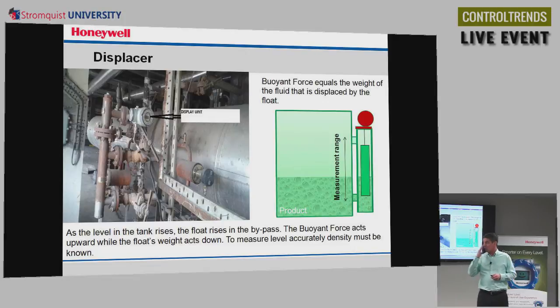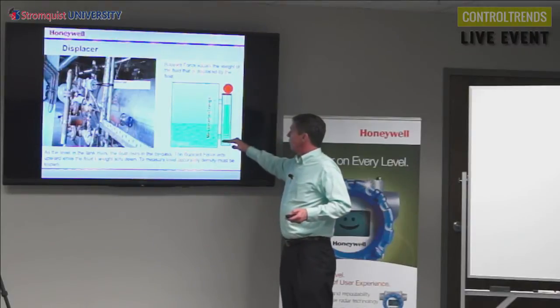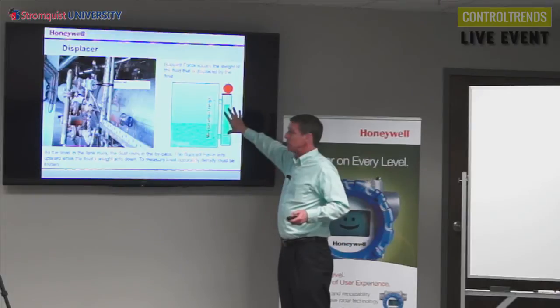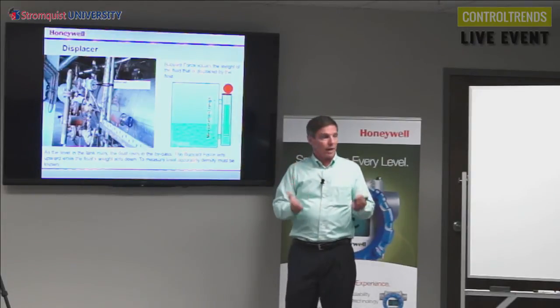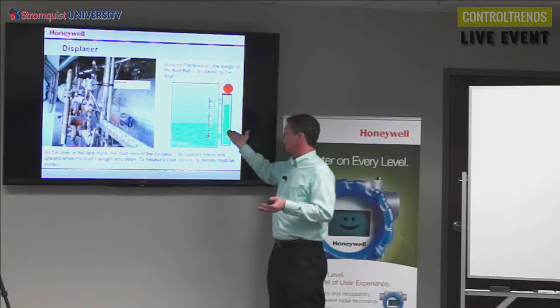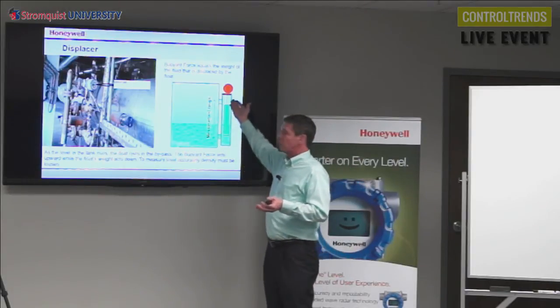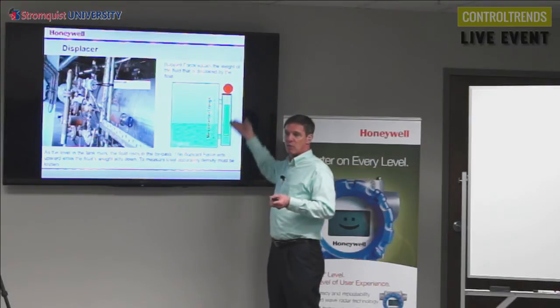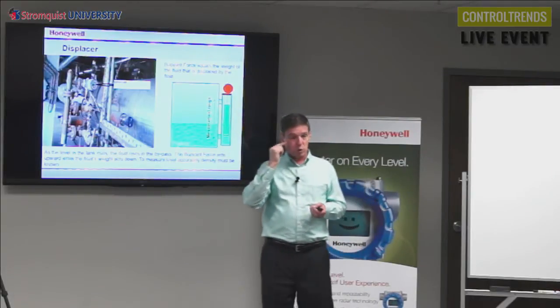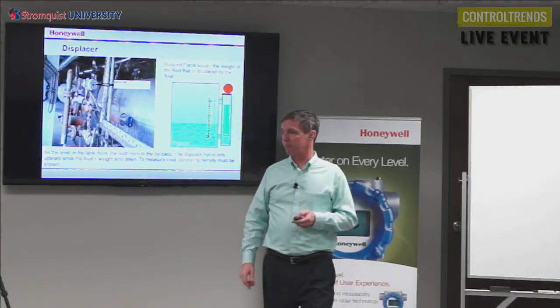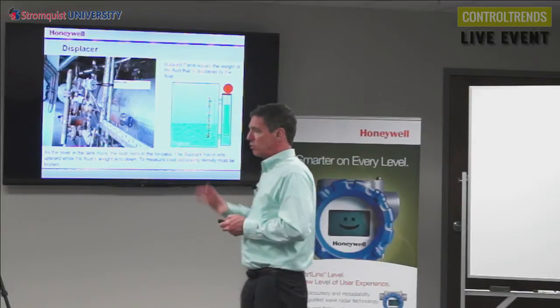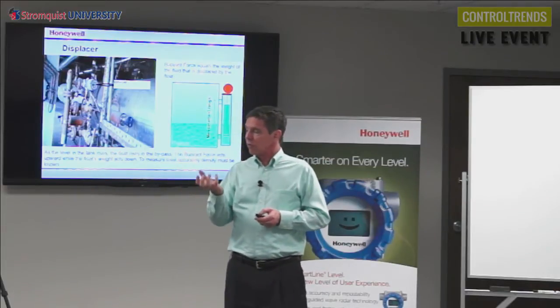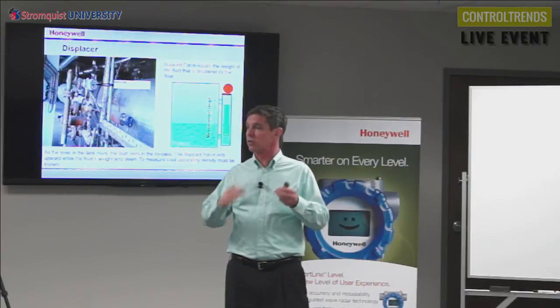But the way this works is off a buoyant force. So we're kind of measuring the weight of that float that's in there. That's a float that's right in the middle. It's on the end of a line. And if there's no fluid in the tank, it's just going to be hanging there, and it'll simply be the weight of that float. But as you add liquid to it, it helps to float it, becomes more buoyant, it pushes it up, that force becomes less. So we measure less force as the level rises. This one is another one that assumes that the density is going to be constant. Okay? Now you'd think that float moves around a lot, but really it doesn't. It's just being moved up by the buoyant force, and it's just a slight movement.